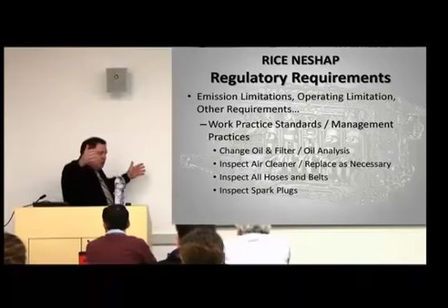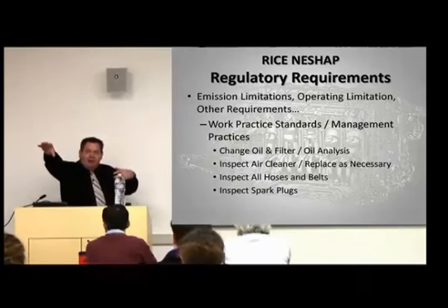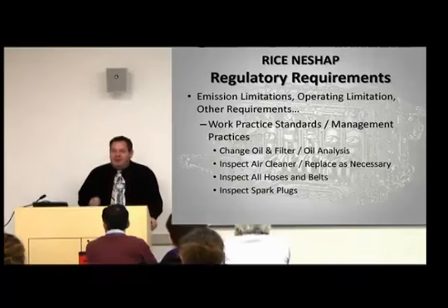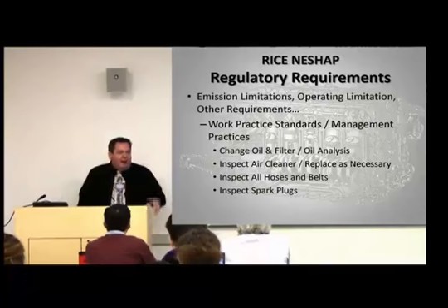Sometimes they have huge drums, like pools, outside of the building containing the engine, and it's full of marbles. Like some of the older people in this room will know, a marble's a little round glass thing you used to play games with. There have got to be 10,000 marbles in this thing, and they have water flowing over it. Not only is that the air cleaner, because whatever solids have to go through all these wet marbles, which separates the solids from the air, but it also controls what they call the charge air temperature, which oftentimes is an emission control strategy for an engine.